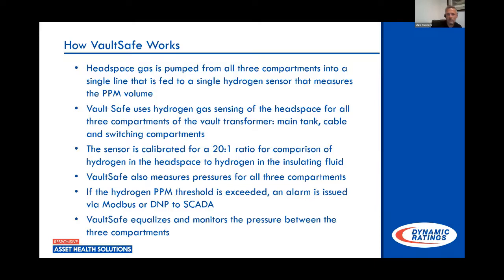Also, one of the advantages of this manifolding system was, with these smaller compartments, the cable and the switch, which we talked about, they're greatly affected by ambient changes in temperature. So if it gets really hot, I've seen switch compartments get up to 7-8 psi of pressure in that compartment if the compartment's sealed well. And again, the cable compartment really doesn't give you any type of pressure measurement, so you really don't know what you're looking at there. But I can guarantee you that as it gets hotter, very small compartment, very small gas space, you're seeing a lot of pressure being generated as that oil and gas expands. And then during the winter, you would go down, and it was not uncommon to see things being in some state of vacuum, due to the colder ambient temperatures.